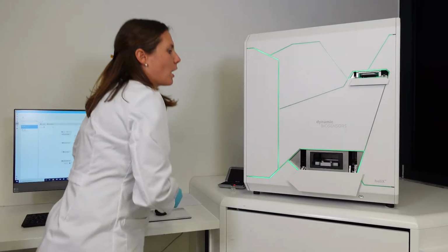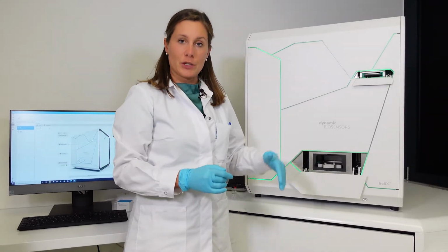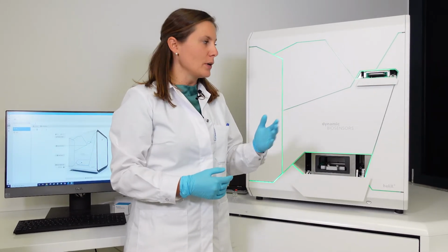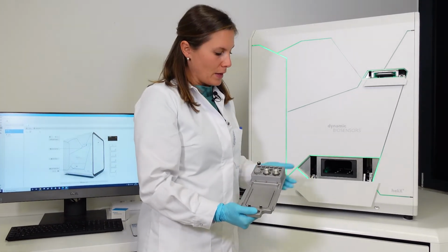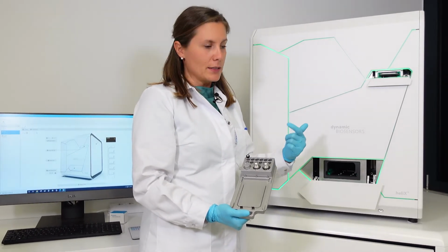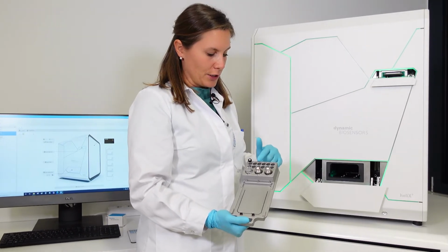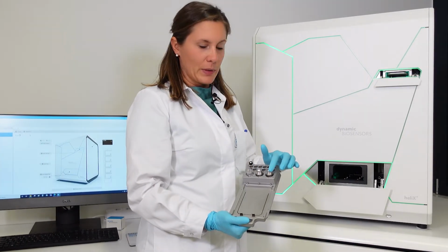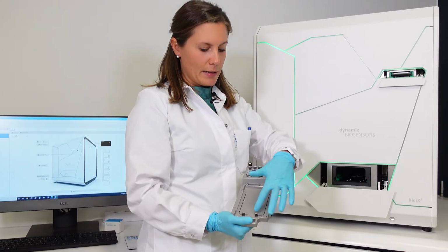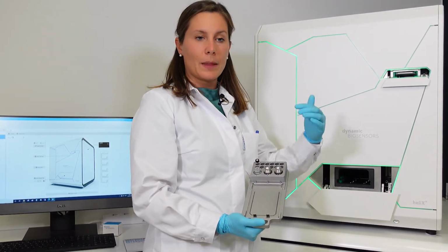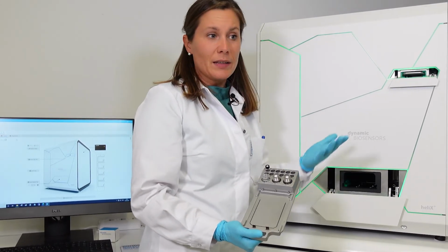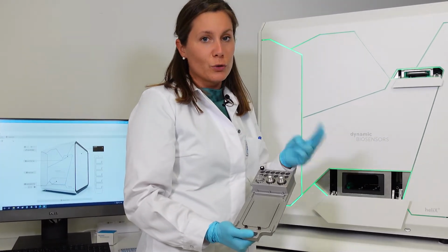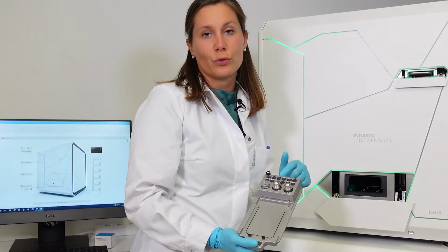Now that our sample tray and chip tray have been ejected, we can place our sample in our chip. So let's start with the sample tray. This is our sample tray. As you see, you can locate the tiny vials up to 1.3 milliliters here in the first part. Then you have big vials with 10 milliliters, and then you have the location for the 96 well plate or 384.